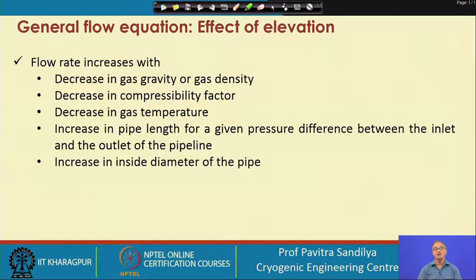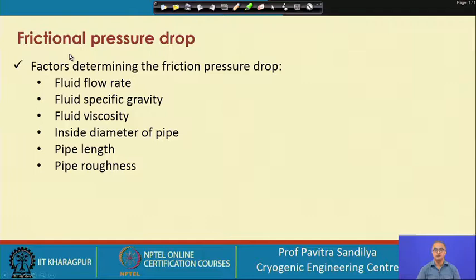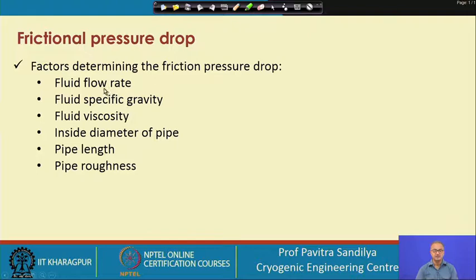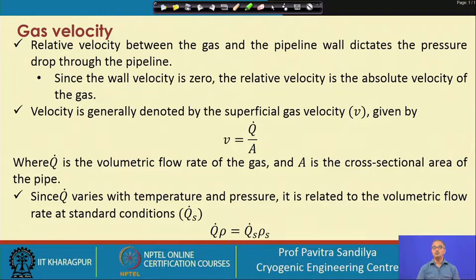The frictional pressure drop depends on the fluid flow rate, the specific gravity of the fluid, the fluid viscosity, the inside diameter of the pipe, the pipe length, and the pipe roughness. These are the common factors that determine pressure drop through a pipeline. To characterize the flow we first need to know the gas velocity, since it is related to the flow rate and determines the flow regime — whether laminar, turbulent, or transitional — through the Reynolds number.